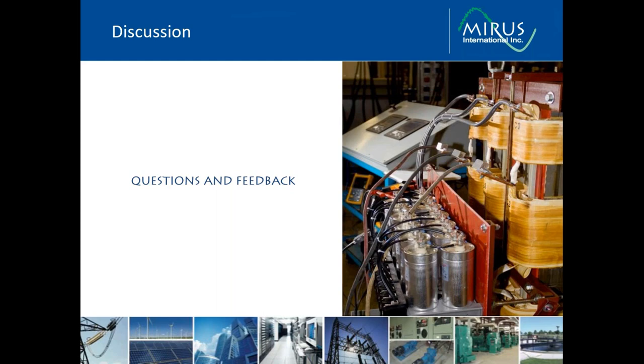Okay. The next question is, someone's asking, they've had issues in the past with passive harmonic filters boosting the voltage at no load, causing overvoltage trips. Has Mirus addressed this issue? Yes, absolutely. There are certainly various manufacturers of input passive filters. Some better than others. There are many that will introduce voltage boost at light loads and therefore require capacitor switching contactors in order to disconnect the capacitors when the drive is lightly loaded. They also can introduce high reactive power that makes them incompatible in generator applications.